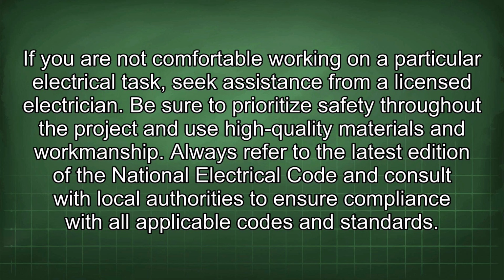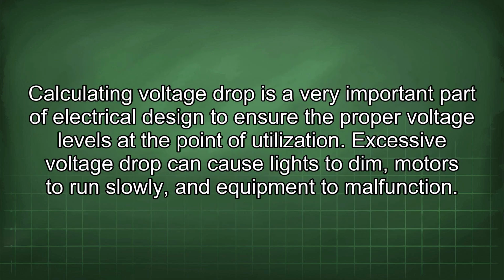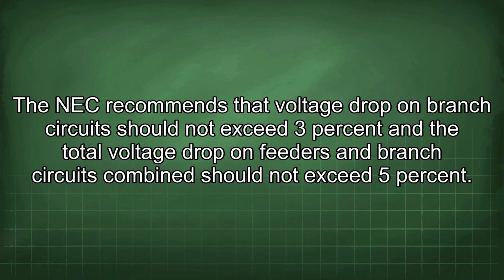Always refer to the latest edition of the National Electrical Code and consult with local authorities to ensure compliance with all applicable codes and standards. Calculating voltage drop is a very important part of electrical design to ensure the proper voltage levels at the point of utilization. Excessive voltage drop can cause lights to dim, motors to run slowly, and equipment to malfunction. The NEC recommends the voltage drop on branch circuits should not exceed 3% and the total voltage drop on feeders and branch circuits combined should not exceed 5%.